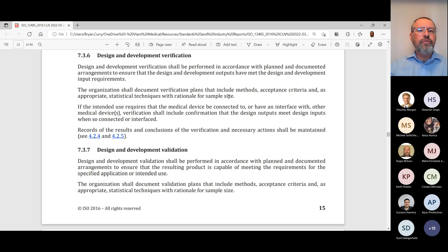Now, most of the time, we see that as an after the fact activity where, when we're writing the report, we look at the data that we have collected and we decide what statistical model we're going to use there. But according to the regulation, you're really supposed to have that captured as part of your protocol. We don't see too many findings around that. If we do, they're generally findings that are wrapped up into a larger statistical techniques type of finding, where maybe your statistical techniques procedure is not sufficient enough. But you really need to be doing some of that work up front if and where you can. And then essentially the same requirements I'll show you here under validation, acceptance criteria, statistical techniques, and rationale for sample size are the same things that are captured as part of verification and validation.